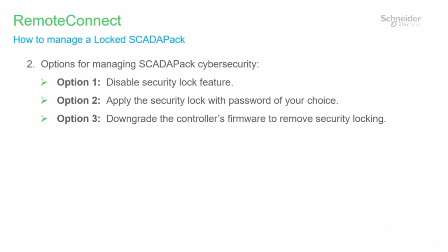Typically, you may want to begin with option 1 to disable the security lock because you will need to have the controller unlocked in order to edit and write configuration changes to it. You may choose option 2 to apply the security lock later after all configuration is completed and the device is placed in the field. Note that the security lock blocks all configuration commands, but protocol access is not blocked for communications with other devices or with the SCADA host. We will discuss option 3 later.